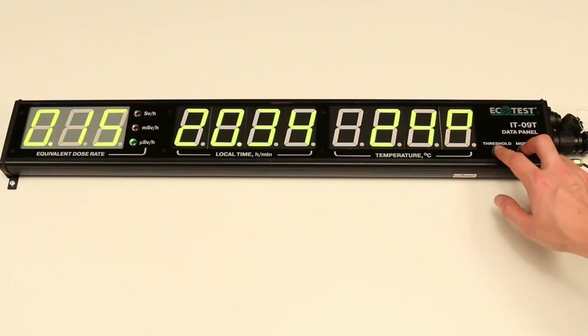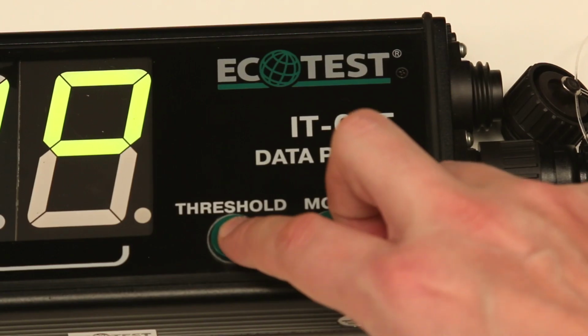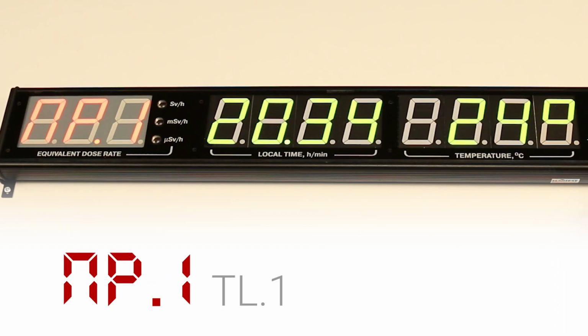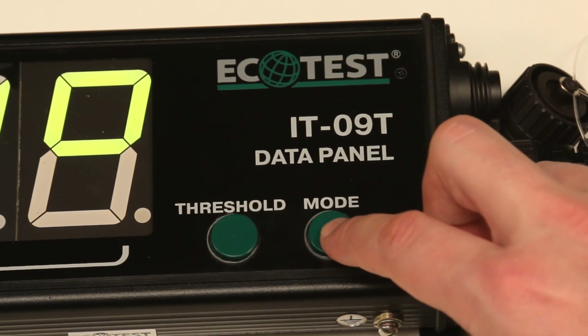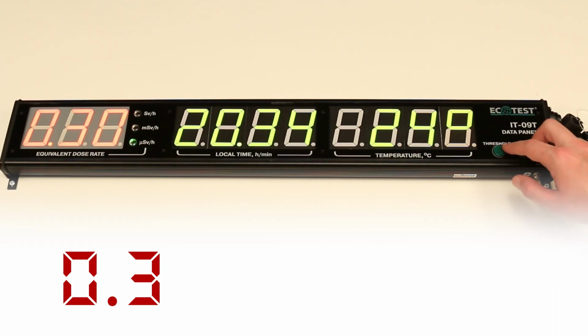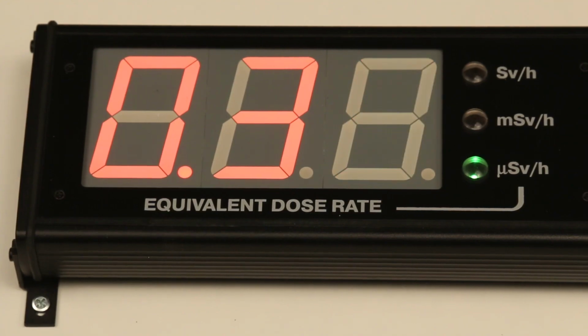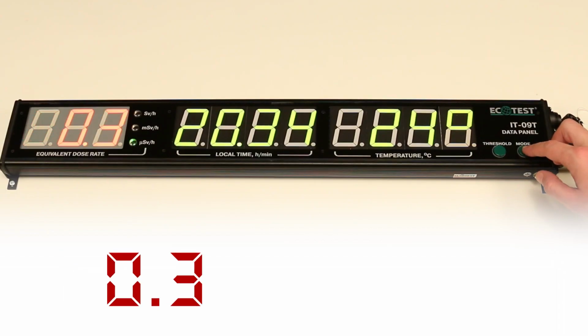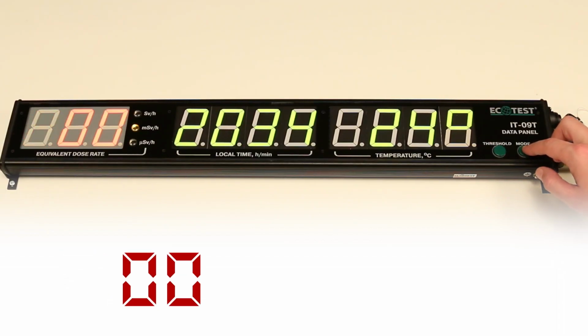How to choose threshold level value? Hold the threshold button for about 10 seconds, and the value of the digit changes to 1. Press mode button to fix the value. Blinking of the next digit makes it possible to change it. After the first three figures of the threshold level are entered, the figures on the dose rate indicator begin to shift from left to right. This enables you to enter values for the major digit positions of the threshold level.